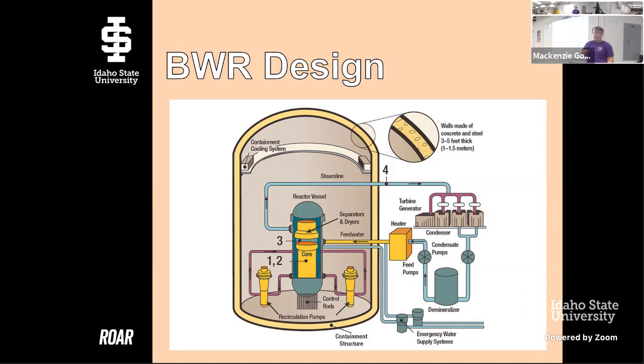We want to ensure that we have very dry, superheated steam when we put it to our turbine, because if there's any moisture, we have low quality steam, little water droplets are going to strike our turbine blades and destroy them. We want pure, dry, all vapor steam.